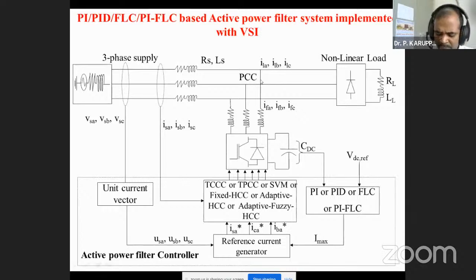So it has 3 modes of operation: mode 1, mode 2, mode 3. In mode 1, the supply voltage is greater than the inverter power supply, that is CVDC or VDC. The VDC voltage is lesser than the power supply. Suppose you are taking 415 volt AC power supply, and it is less than that because initially the capacitance value is very less, or it may be 0 also. Under that condition, mode 1, where the supply voltage is greater than VDC, it will act as a rectifier to recharge the capacitor.